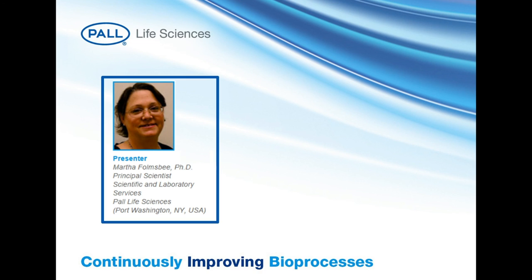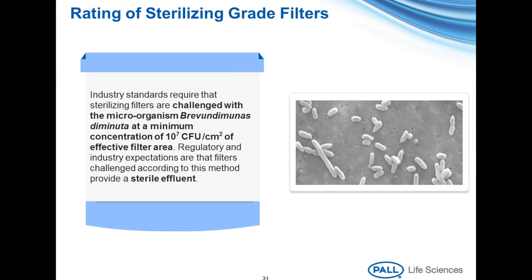The second stage is a process-specific test where the filter is tested under the conditions of actual use with actual product when possible. This is a filter validation or filter qualification test. The integrity test—like a forward flow or bubble point—is performed on the individual filter at the time of use. Both sterilizing filter rating tests and most process-specific tests are usually performed with Brevundimonas diminuta, as specified in the ASTM standard—the standard test method for determining bacterial retention ratings of membrane filters utilizing liquid filtration.